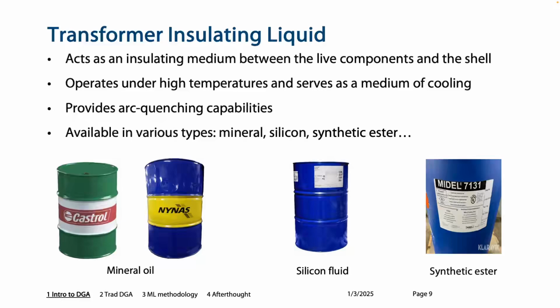It also provides arc quenching capability because, as I said, when electrical sparks appear inside the transformer, it absorbs some of that energy and decomposes the oil into gases. There are various types of oil - in MTR, mainly mineral oil, silicon oil, and synthetic ester.